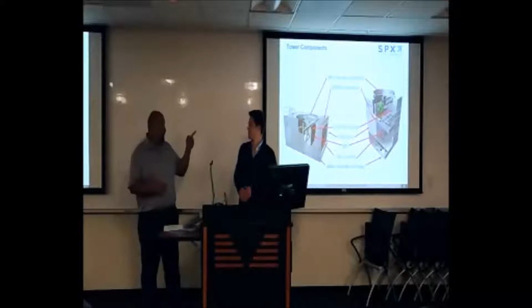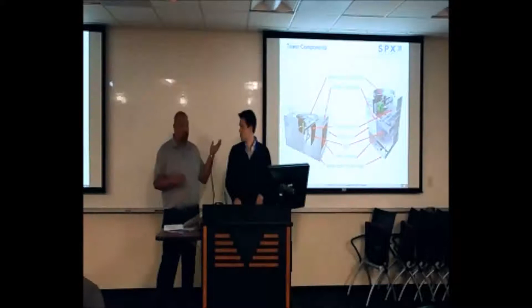Back on the fill, USC decided they're familiar with the Marley type of tower and wanted a catwalk to make it easier to clean the fill. The towers you guys received are double stacked, what we call double stack. It looks like two towers stacked together, but it's just taller fill, one of the larger towers. So you have a catwalk that runs in front of the 3 cells on both sides.